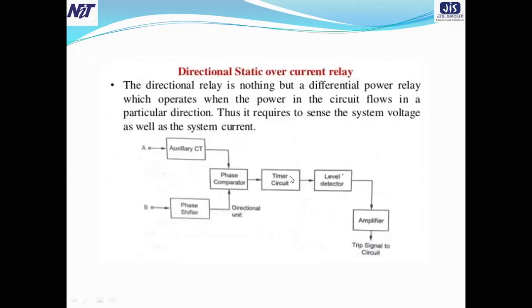Now the next one, the directional static overcurrent relay, is nothing but a differential power relay, so both are similar. A differential power relay operates when the power in the circuit flows in a particular direction, so it requires sensing the system voltage as well as the system current.